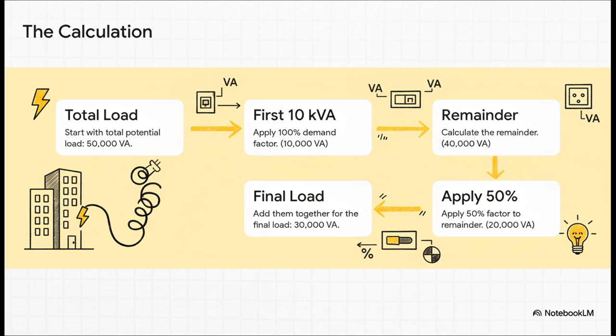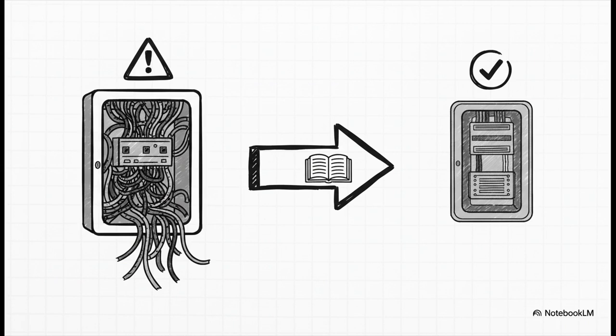That leaves us with a remainder of 40,000 VA. Now we apply our 50% demand factor to that remainder, which gives us 20,000 VA. So you add the two parts together, and our new, much smarter load is 30,000 VA. Just like that, we've cut our required capacity by a massive amount.